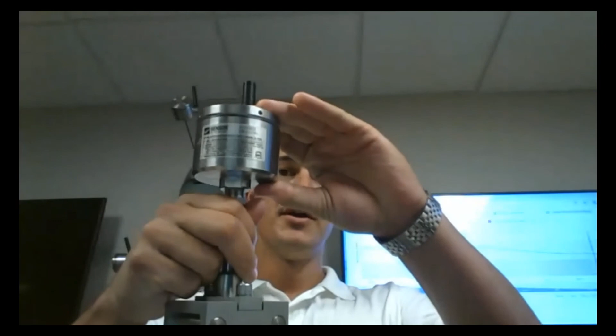What are the temperature limitations, and is there a device installed for temperature compensation? I think I answered that as well. On each one of these items there are two temperature sensors: one on top telling you the temperature inside the housing, and the other at the bottom, so you have two different temperature devices. Temperature limitations, as I mentioned, run from -40 F or C up to 150 C, and depending on whether you want them permanent or temporary you can make some changes. The high temp sensors go from -40 up to 500 C, and they're permanent or temporary regardless.